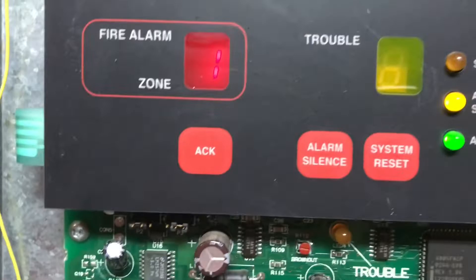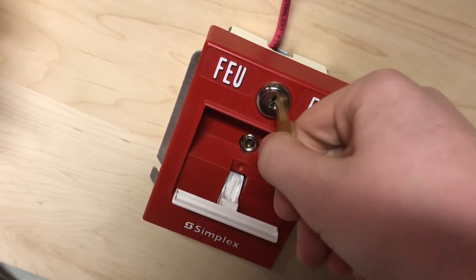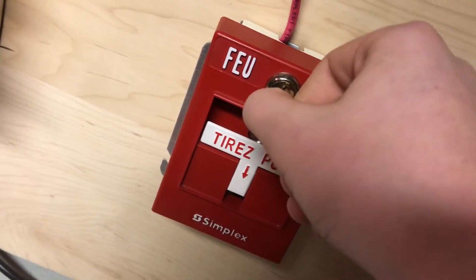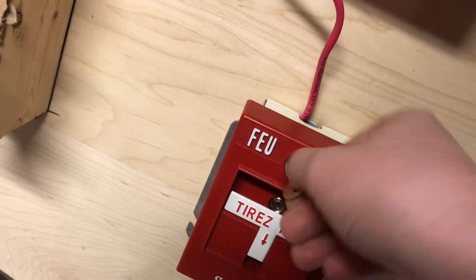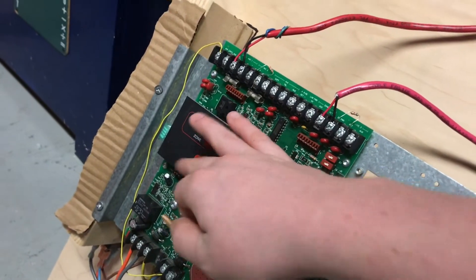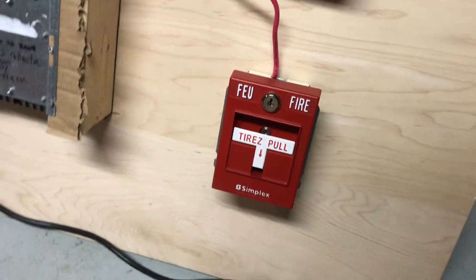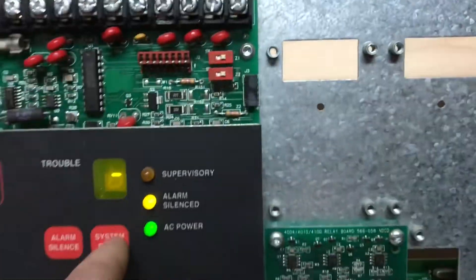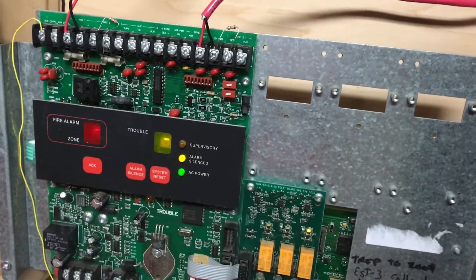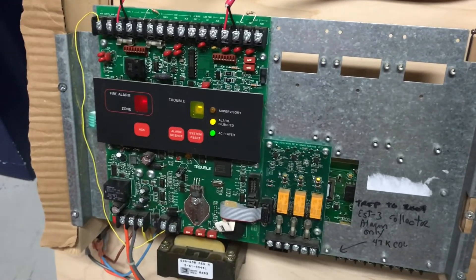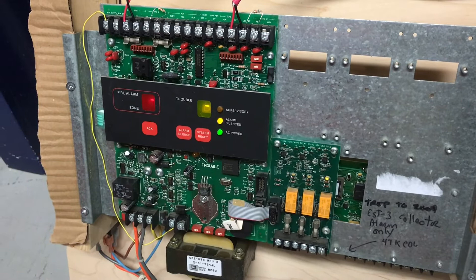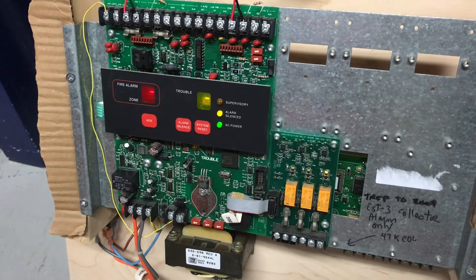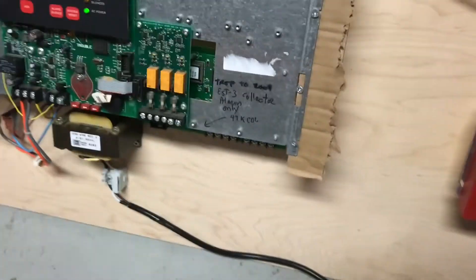It says zone 1 for alarms. Let's go ahead and reset the pull. A nice thing about this panel is it has re-alarm. So, you can re-alarm a zone, and it will go back into alarm. And then you click reset. And then it takes about 10 to 15 seconds to reset. We'll just wait for that.